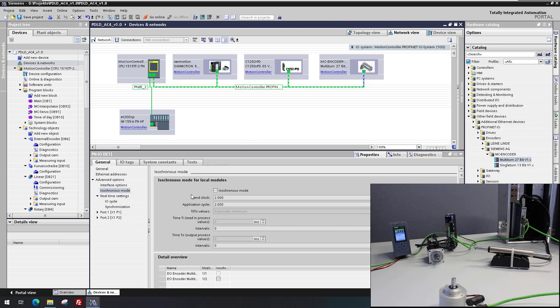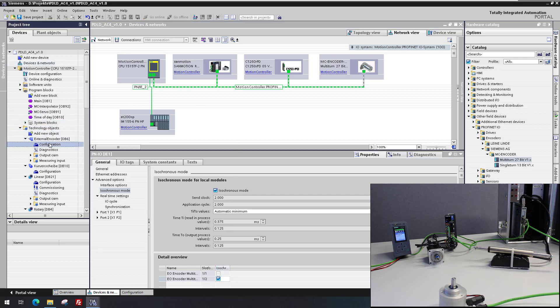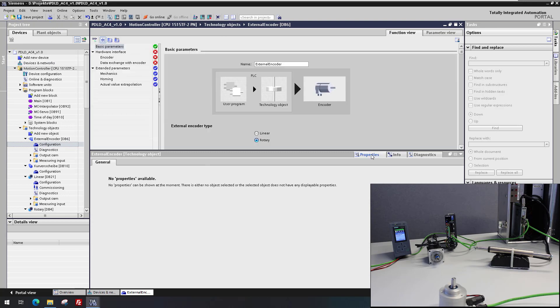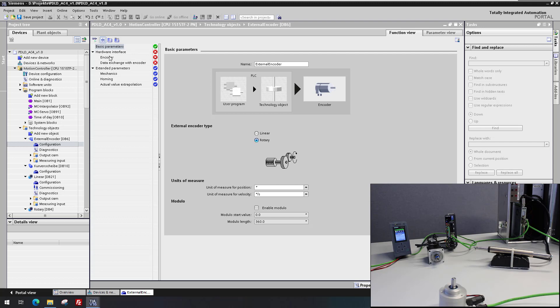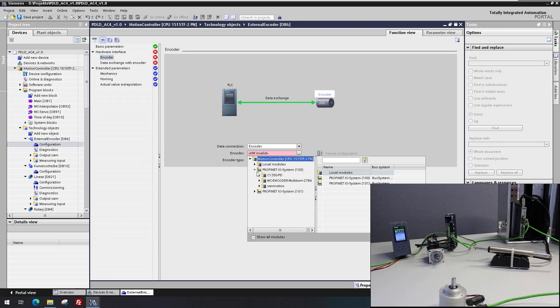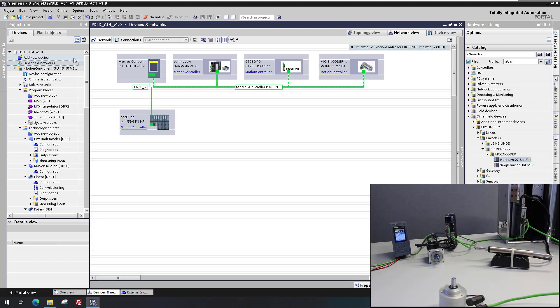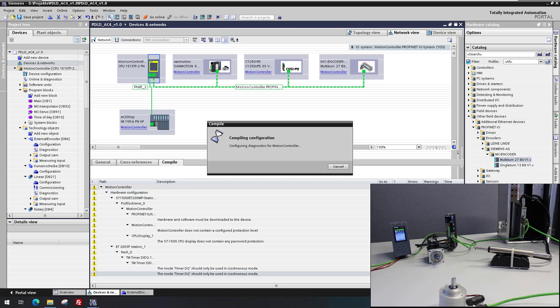The device is configured to run in isochronous mode. The second adjustment step relates to the technology object for the external encoder, where the hardware interface must be adjusted to the newly inserted device and its configured telegram. After that, the changed configuration can be compiled and loaded into the motion controller.